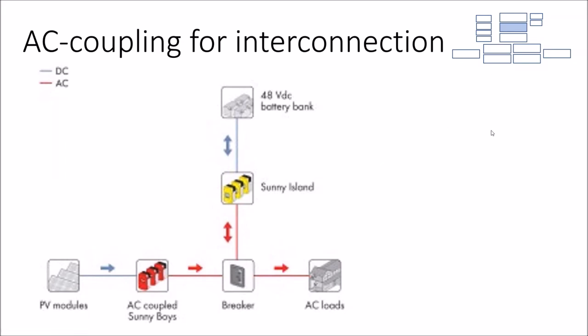With AC coupling, you go from the modules into the service panel, into the load, or into the grid. So it's a one-step process from the modules through the inverter to the point of use. Whereas if we're running off our batteries under AC coupling, it's a three-step process: from the modules through the inverter, through the battery inverter, and then back down.